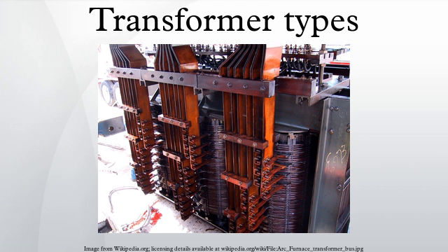A combined instrument transformer encloses a current transformer and a voltage transformer in the same transformer. There are two main combined current and voltage transformer designs, oil paper insulated and SF6 insulated. One advantage of applying this solution is reduced substation footprint, due to reduced number of transformers in a bay, supporting structures and connections, as well as lower costs for civil works, transportation and installation.